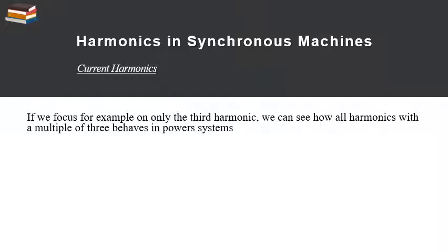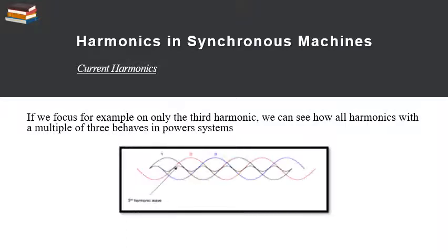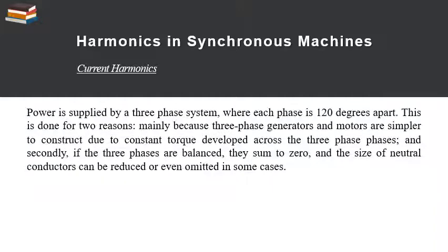If we focus, for example, on only third harmonics, we can see how all harmonics with a multiple of 3 behave in a power system. So this is the waveform. In this, we can see the third harmonic wave. The power is supplied by a 3-phase system where each phase is 120 degrees apart.